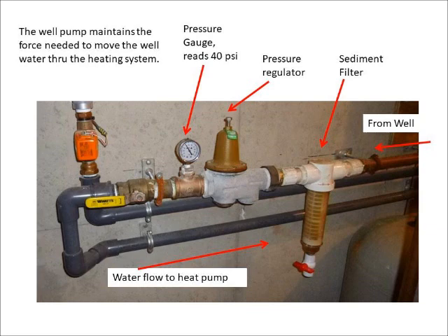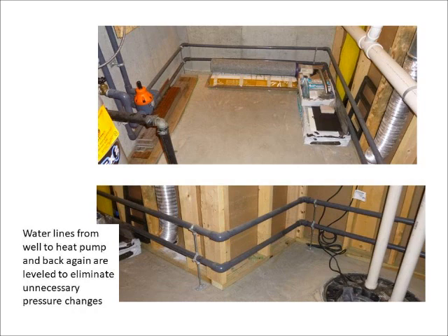The incoming water from the well enters on the right in this view, passes through the sediment filter, pressure regulator, pressure gauge, and a control valve before flowing to the heat pump on the bottom PVC pipe. The combination of the pump maintaining a certain pressure in the system and the setting of the pressure regulator accounts for all the pressure drops in the system for peak performance of the heat pump system. The water lines from the well to the heat pump and back again are leveled to eliminate unnecessary pressure changes.